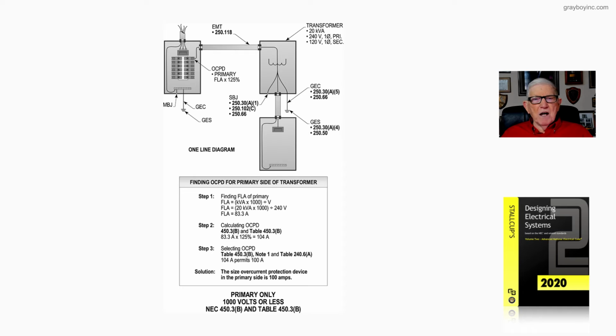You have the main bonding jumper size. You have the grounding electrode conductor size connected to the grounding electrode system. Then you have the system bonding jumper sized properly in accordance with 250.30(A)(1), 250.102(C), and 250.66. The grounding electrode conductor is basically sized and determined in 250.30(A)(5) and connected to the electrode, which is in 250.50. But you have your sections here to complete the complete installation when you start the design.